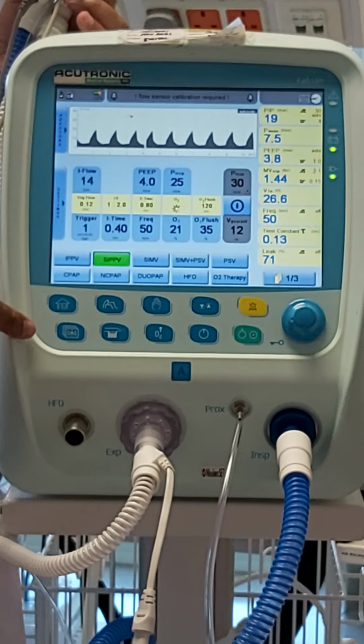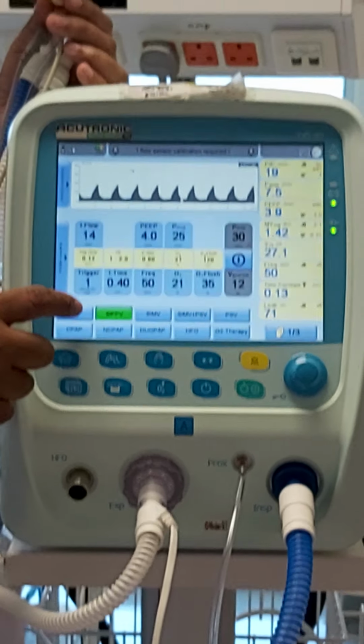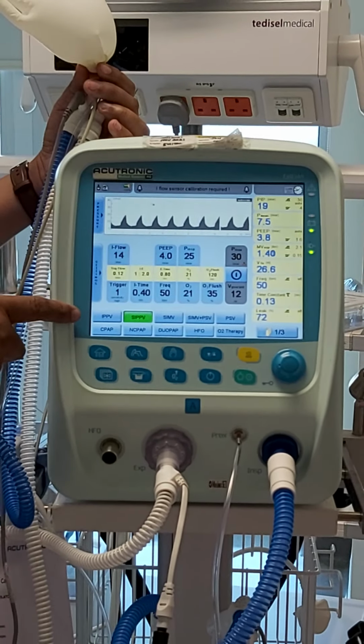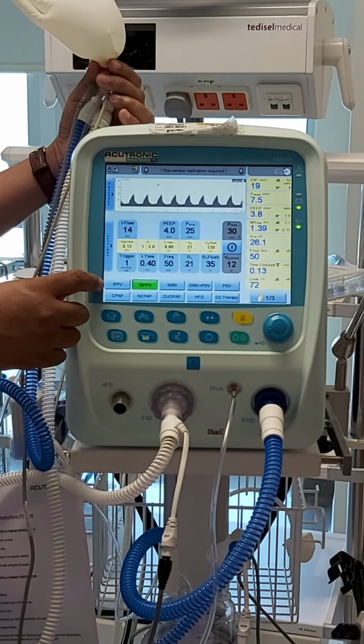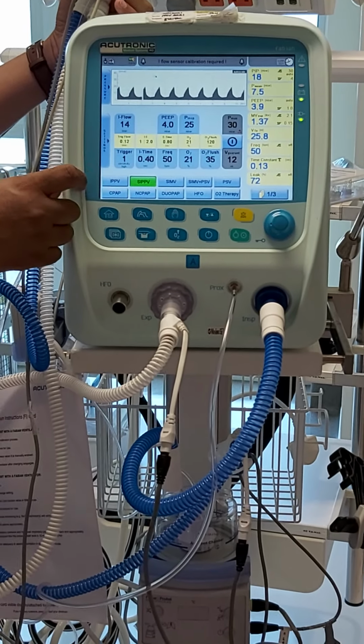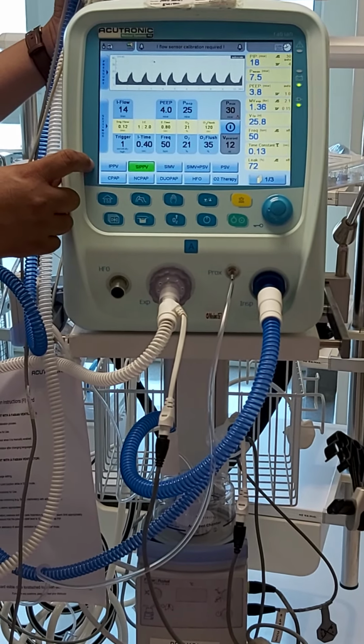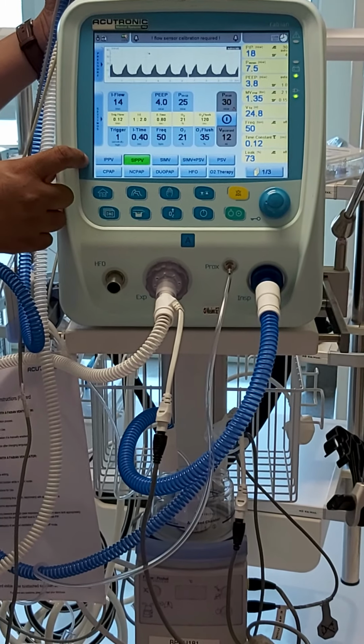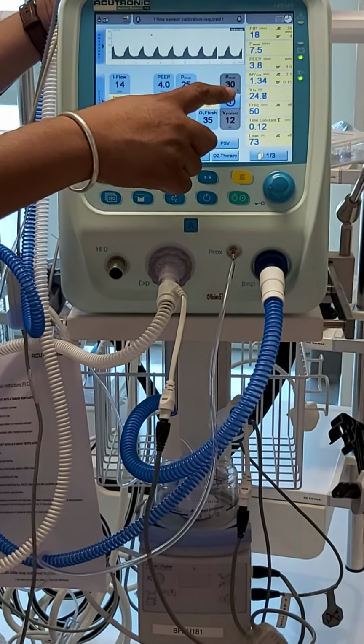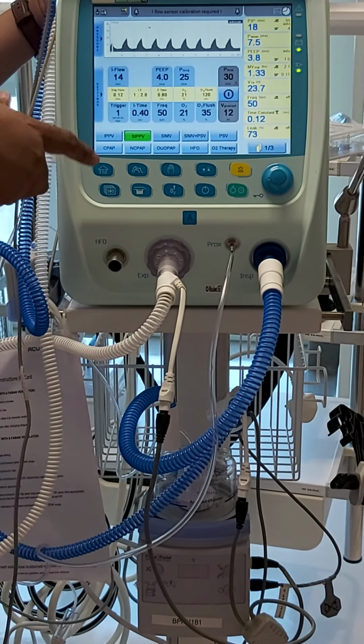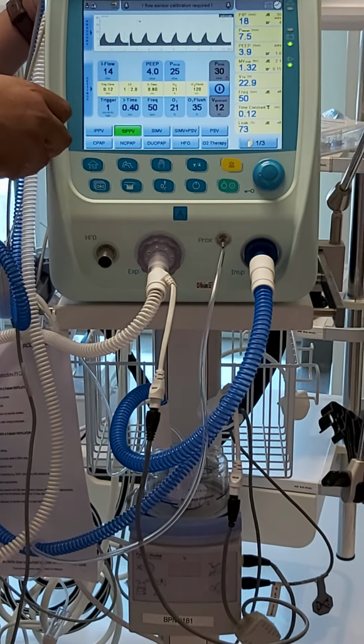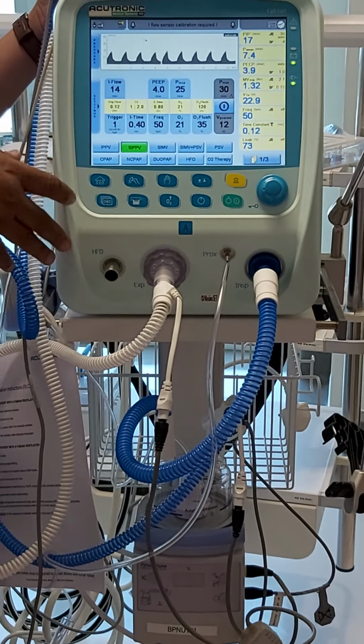So what you do now when you have this machine, you have to first select or ask the doctor what mode you will use. Do you want your IPPV or your SIPPV? If you notice, all of the modes are in pressure. The reason is that you can turn on your volume guarantee every time. Once you turn on the volume guarantee, you will have a volume mode. If the volume is not on, then it's a pressure mode.